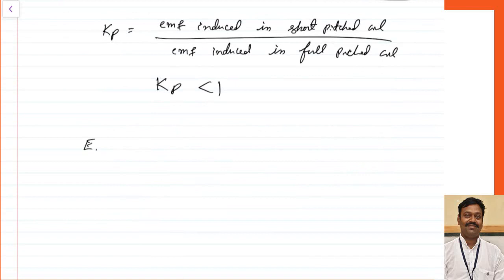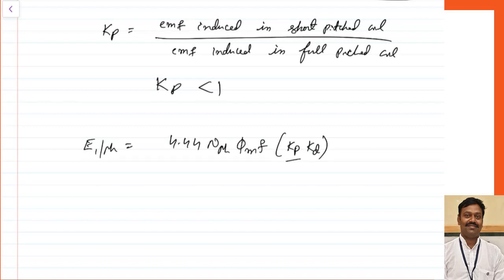If you want to calculate the net EMF because of the distributed winding, whatever is the EMF in concentrated winding — 4.44·N_phase·Φ_max·f — you have to multiply with both the pitch factor Kp and the distribution factor Kd. If it is a full pitched coil, Kp equals 1; if it is short pitched, Kp equals cos(α/2). The product of Kp and Kd is called the winding factor Kw, because both factors arise from the type of winding employed.